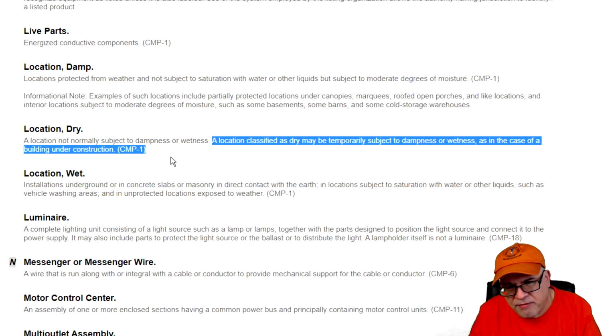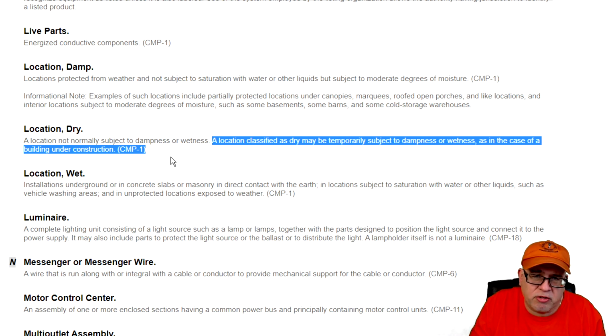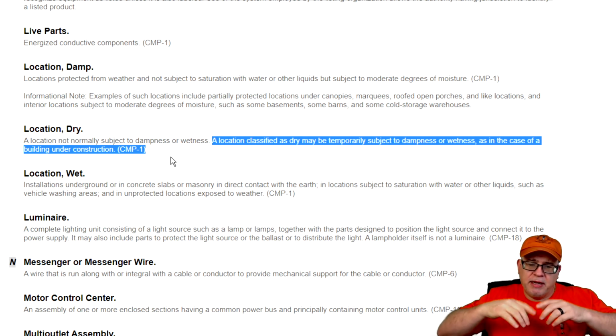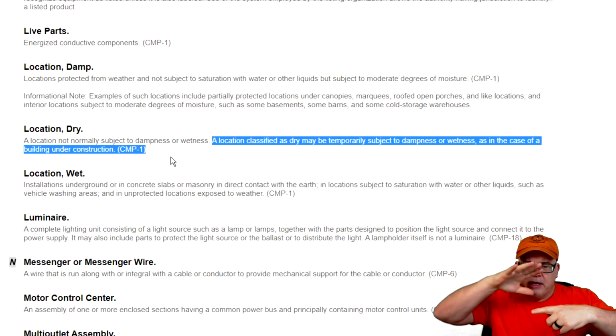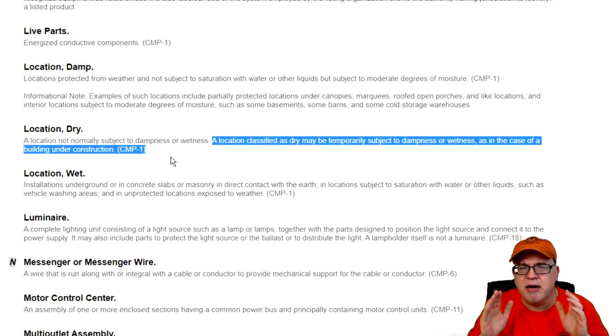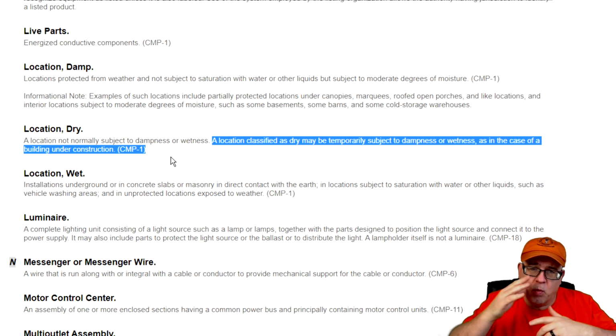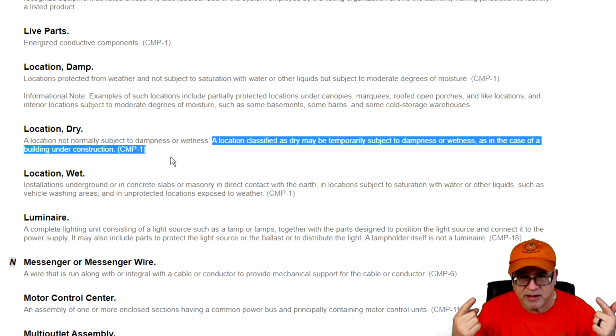But the reason we have this statement here is it says that it's a dry location, but it can be subject to temporary conditions of dampness and wetness, and even gives you an example of a building under construction. And again, it says that's just an example. That's not all potential cases. So, again, the caveat to this is contact your manufacturer if you run into this condition and let them give you guidance on it. But just because wire, let's say it was in a ceiling of a 2-story building and a sprinkler system went off and the water came down and you have horizontal non-metallic sheath cable and some water came over top of it. Am I really going to rip all that out just because it got exposed to some water? Absolutely not. Now, the ends didn't get caught up in it.